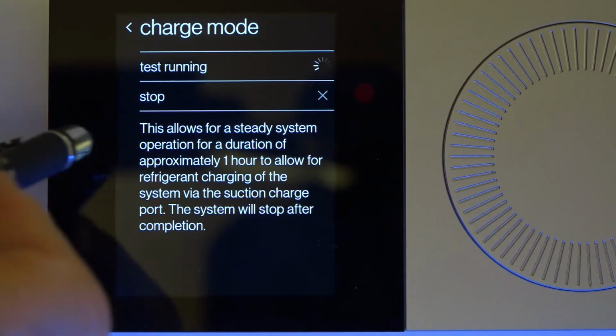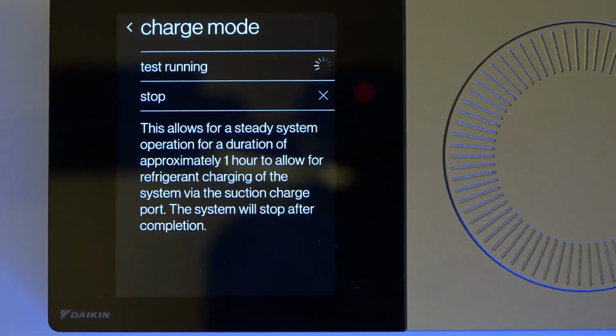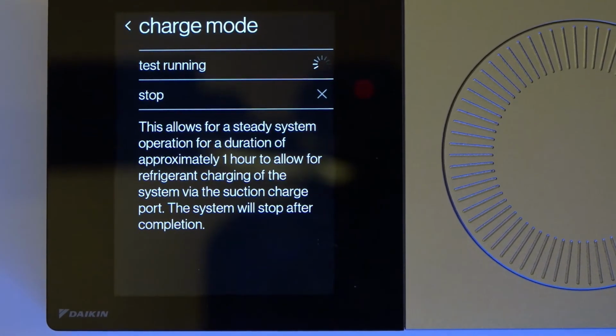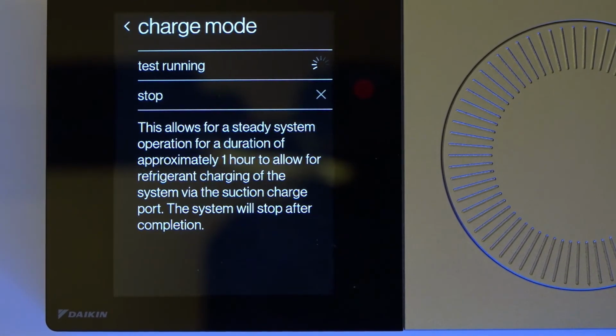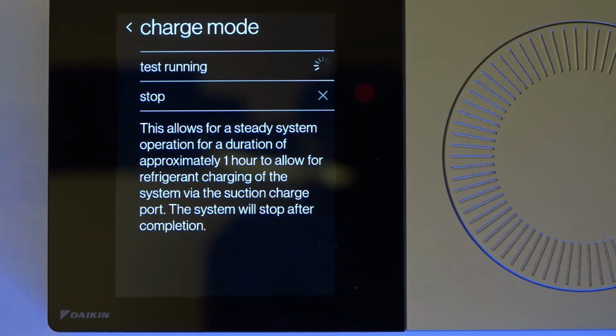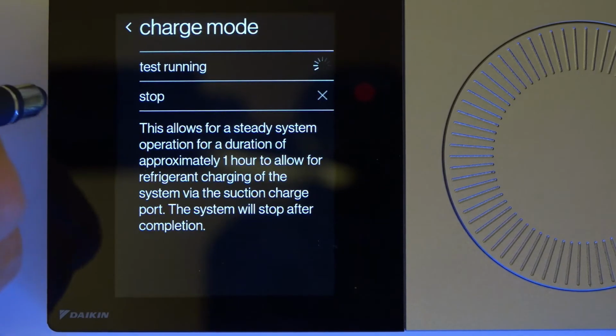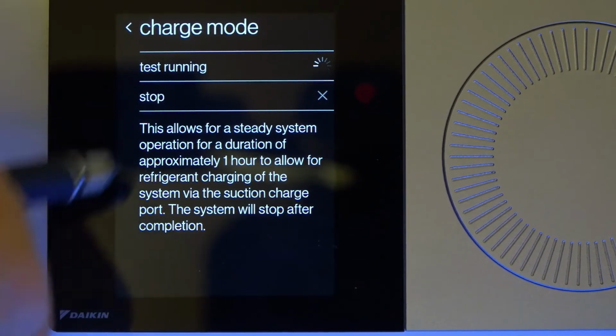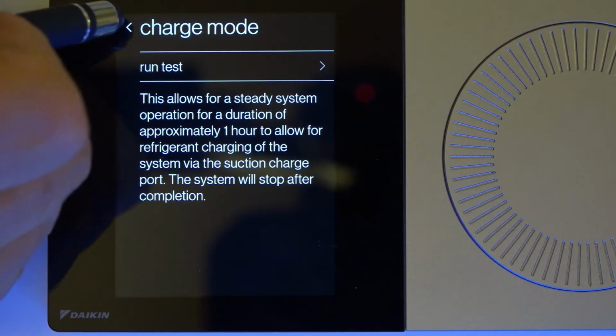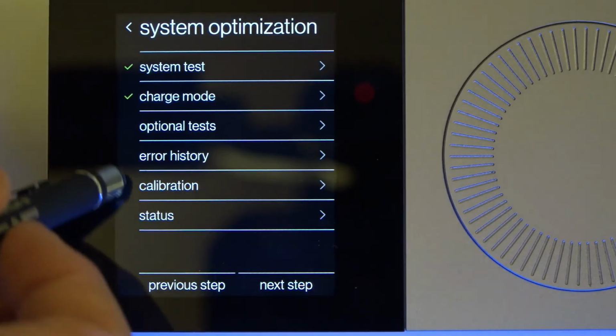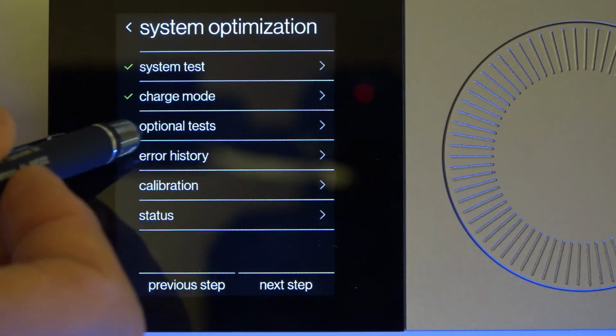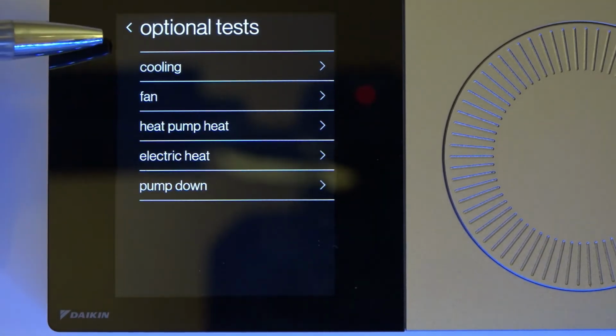And then if I finish up, this test will run for 60 minutes. So if I left it in there for the whole 60 minutes, it would stop on its own and end the test. But anytime after I get my subcooling set, I can come in here and hit stop test, and that ends it. If I had any other optional tests I want to run, I could test the cooling.